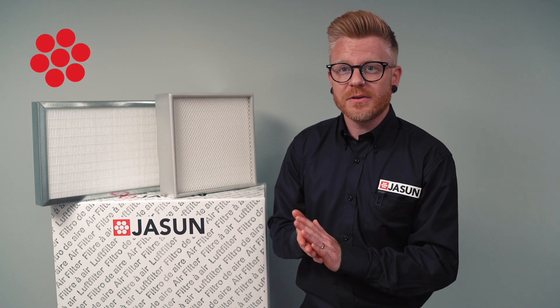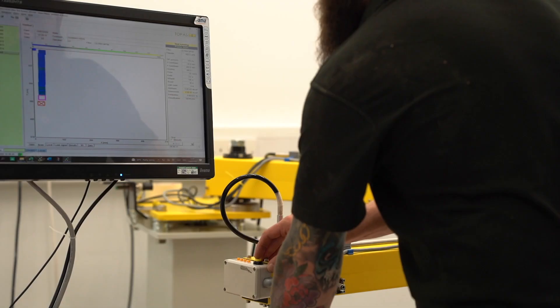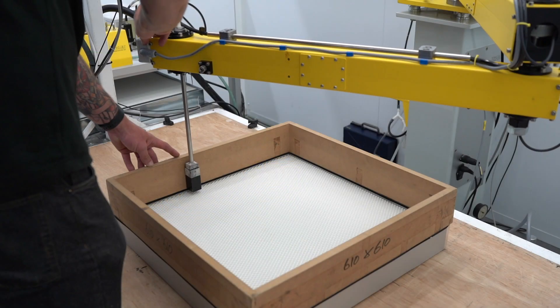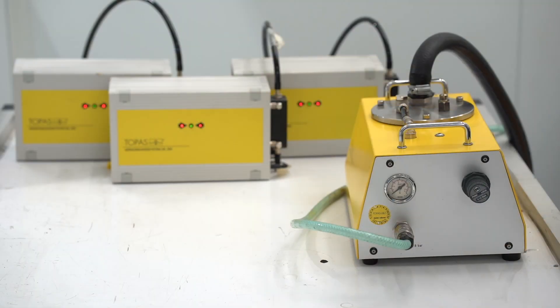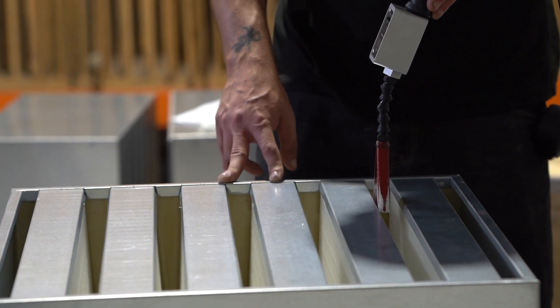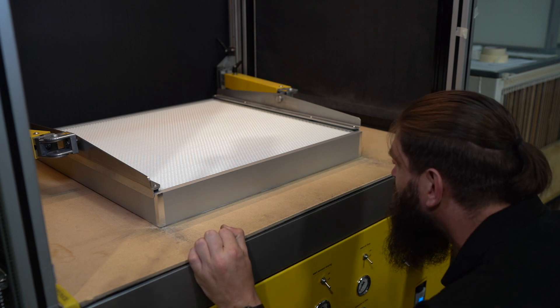Every single HEPA filter we manufacture at Jasun is individually tested by one of our in-house experts. We challenge each filter with a very specific aerosol, which is blown into the filter on one of our test rigs. We then scan the filter using calibrated instruments to measure what percentage of the aerosol has managed to get through the filter. This ensures that there are no leaks or breakthroughs that exceed the strict standards required.